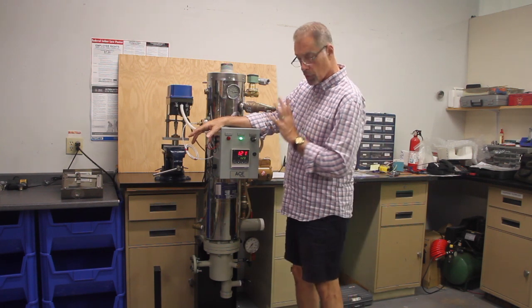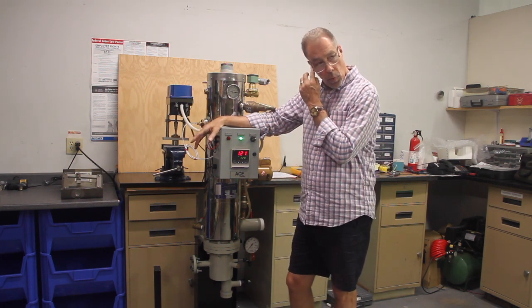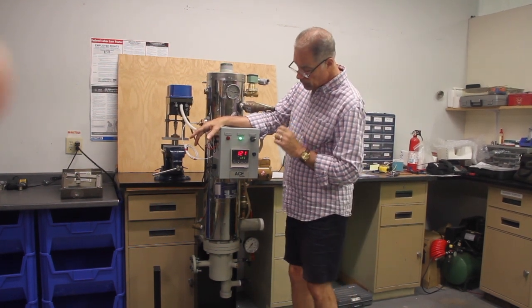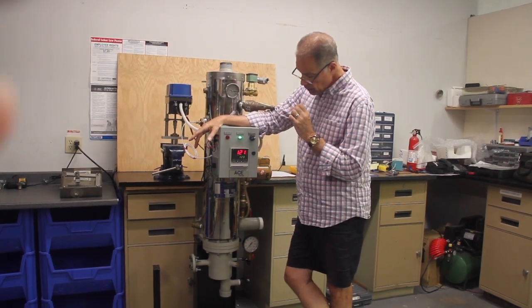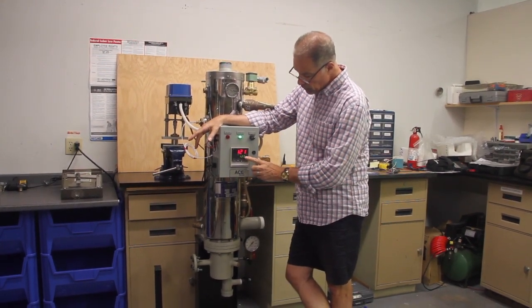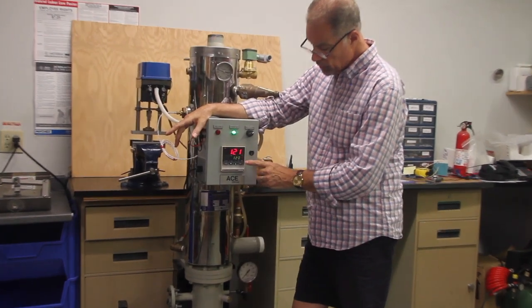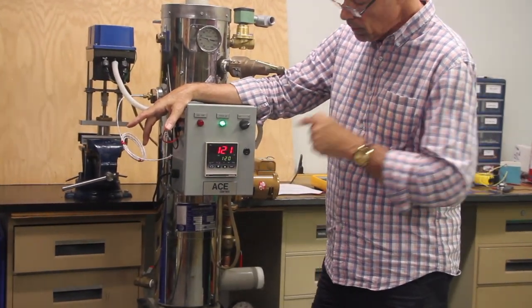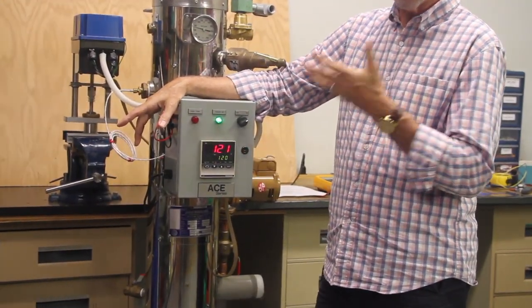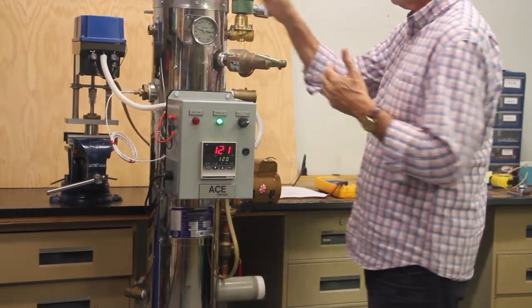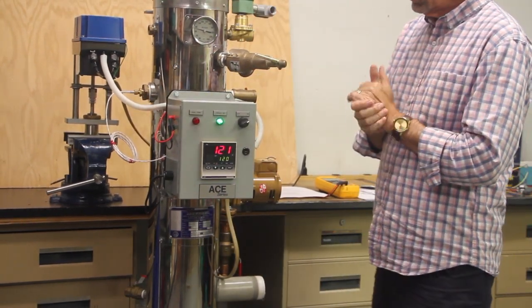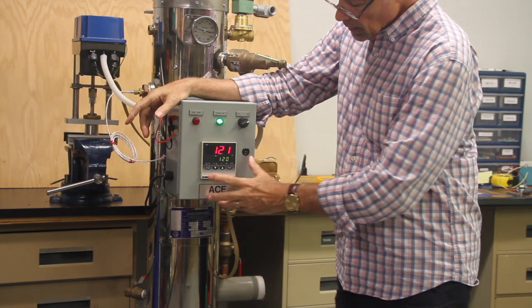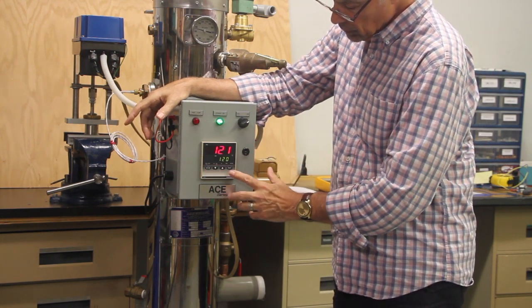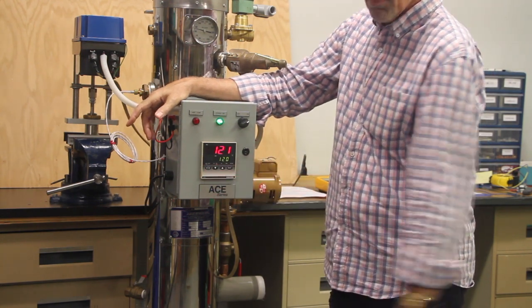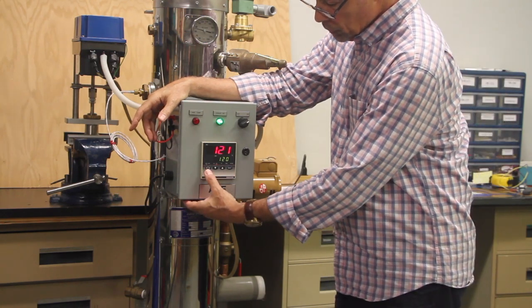But let's go through the controller settings real quick. They're really basic. There's two screens. What you need to be aware of is really the first screen. The first screen shows the set point temperature, in this case 120. The actual water temperature in this case is 121. We're not actually filled with water here. We're running off a calibrator. There's a left button, a right button, and up and down buttons.